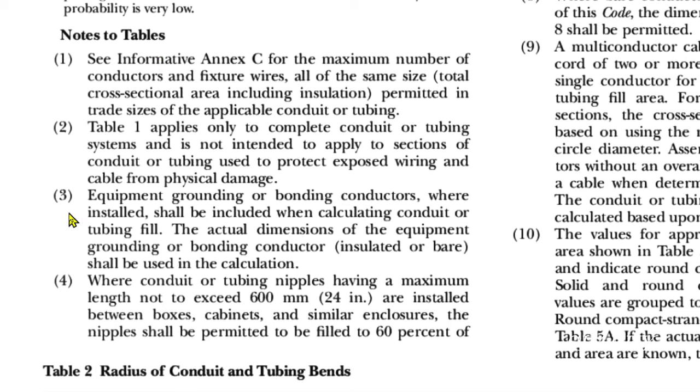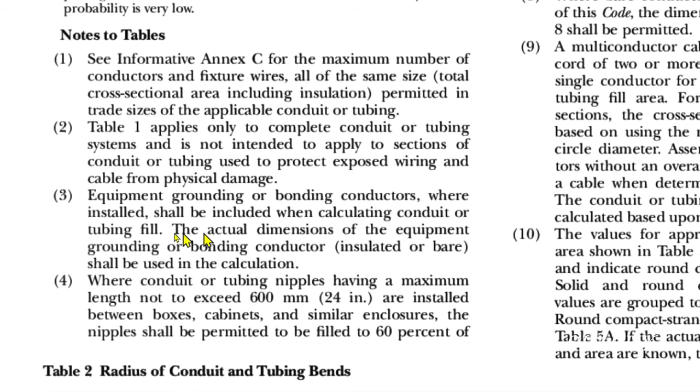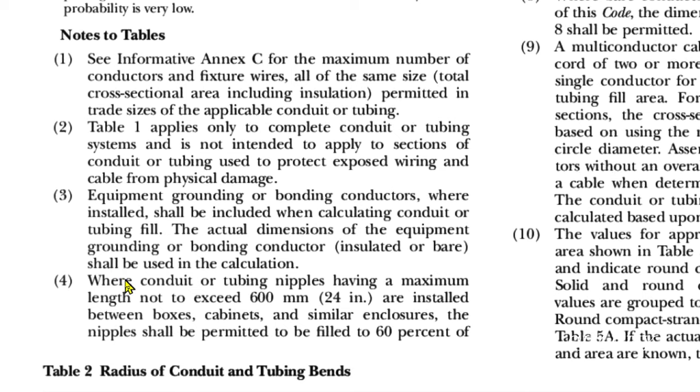Right below Table 1, Notes to Tables number three: 'Equipment grounding or bonding conductors, where installed, shall be included when calculating conduit or tubing fill.